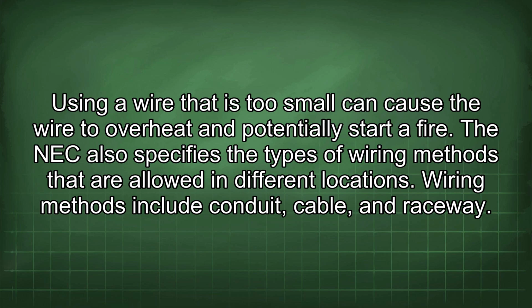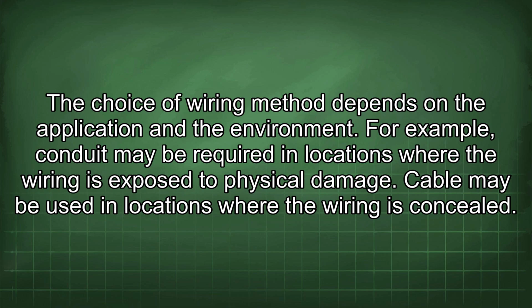The NEC also specifies the types of wiring methods that are allowed in different locations. Wiring methods include conduit, cable, and raceway. The choice of wiring method depends on the application and the environment. For example, conduit may be required in locations where the wiring is exposed to physical damage. Cable may be used in locations where the wiring is concealed.